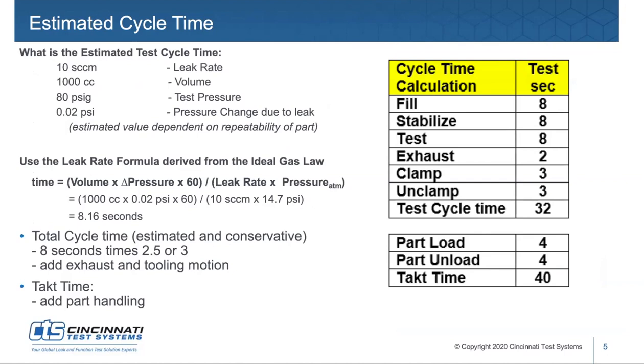That volume times delta P, a pressure change that will be measured using pressure decay. We look for a 0.02 PSI as a conservative factor, times 60 seconds per minute. That quantity divided by leak rate, that's the volumetric flow of air from the part, times pressure, which is atmospheric pressure at sea level. That standardizes this whole formula to standard conditions. In this case, we've got an example that a 0.02 psi drop for a liter part equals 8 seconds.